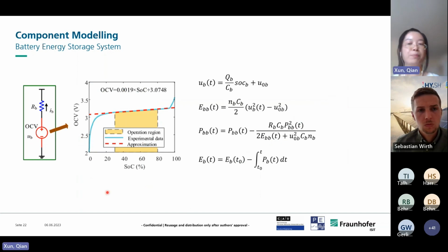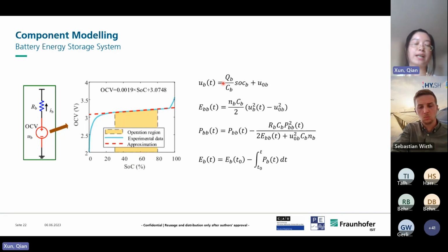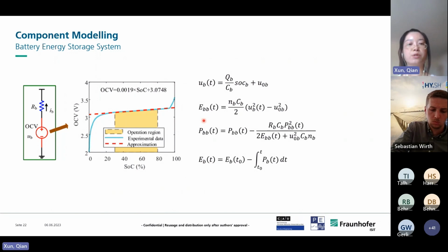For the battery, it can be modeled by an open circuit voltage connected in series with a resistor. This shows how the open circuit voltage changes with the state of charge. If we consider the state of charge range between 30% and 80%, the open circuit voltage changes linearly with the state of charge. From this, we can get the terminal voltage of the battery, the internal battery energy, and the battery terminal power. There is also dynamics between battery energy and power, where battery energy is the integration of battery power.